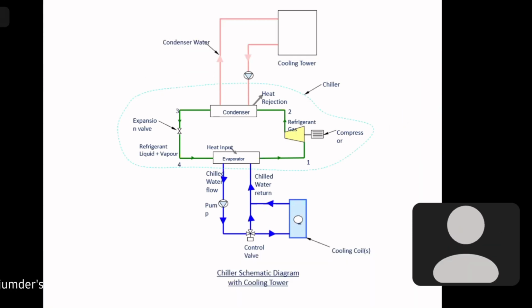So air and water maintain a cross flow. Water is coming from the top and air moves from bottom to top or across the water flow. It cools that spray of water coming from the top of the cooling tower. The hot condenser water gets cooled, and it is collected at the bottom of the cooling tower, in the cooling tower basin. We take it by a pump and flow it through the condenser. So it's a water-cooled chilled water system.